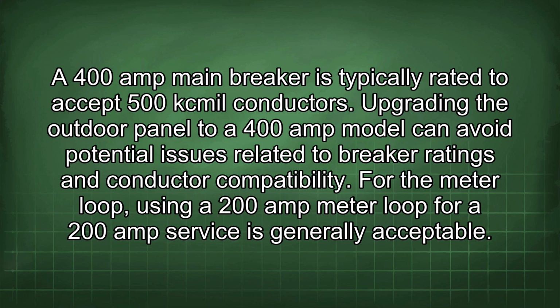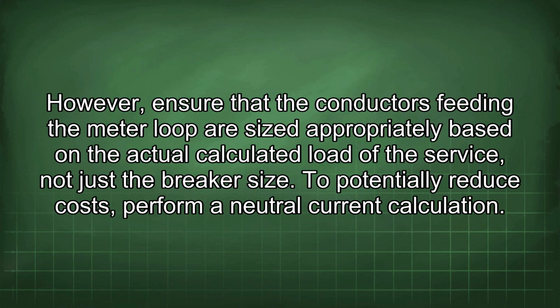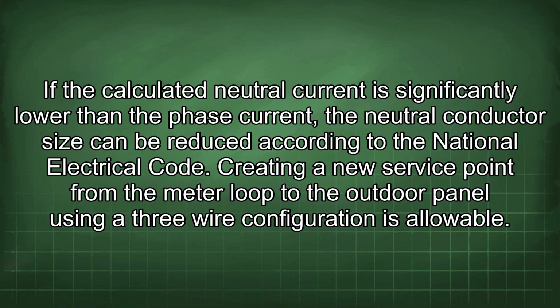For the meter loop, using a 200 amp meter loop for a 200 amp service is generally acceptable. However, ensure that the conductors feeding the meter loop are sized appropriately based on the actual calculated load of the service, not just the breaker size. To potentially reduce costs, perform a neutral current calculation. If the calculated neutral current is significantly lower than the phase current, the neutral conductor size can be reduced according to the National Electrical Code.